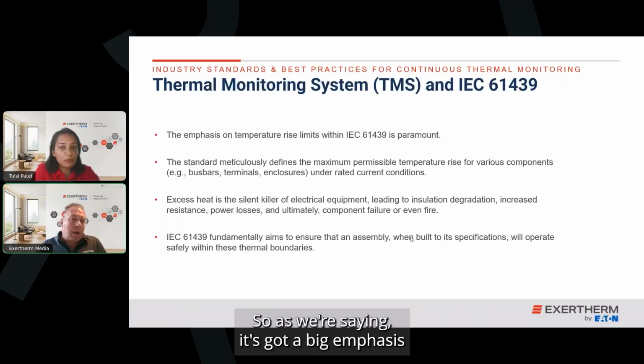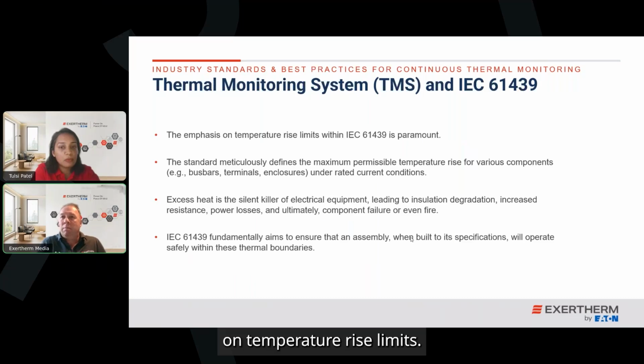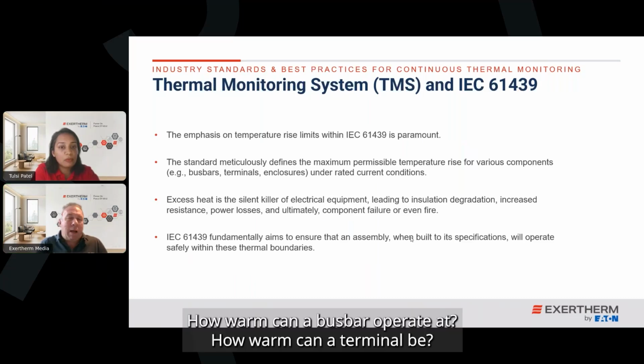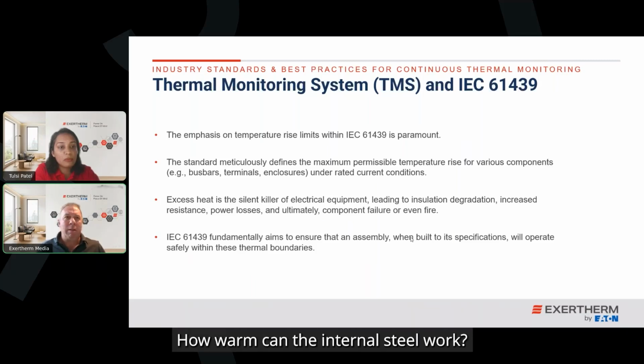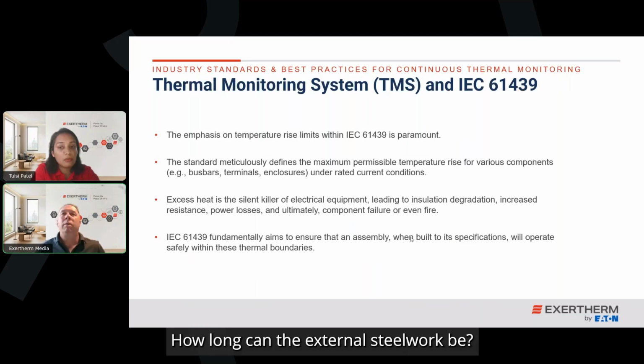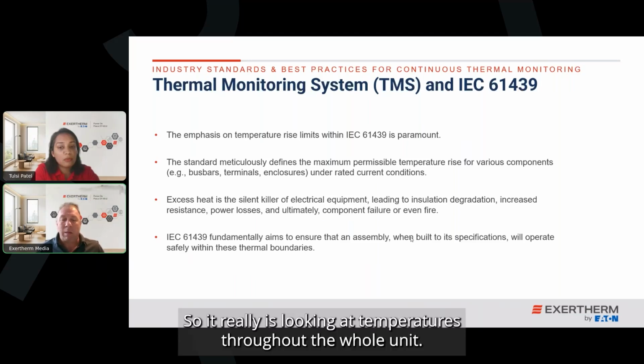So as we're saying, it's got a big emphasis on temperature rise limits. How warm can a bus bar operate? How warm can a terminal be? How warm can the internal steel work be? How warm can the external steel work be? So it really is looking at temperatures throughout the whole unit.